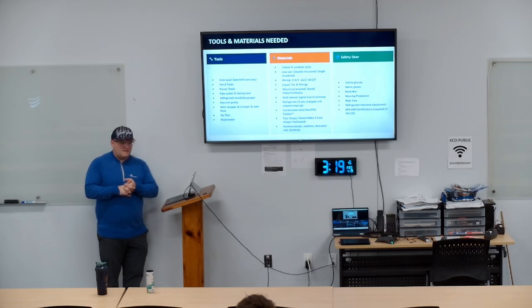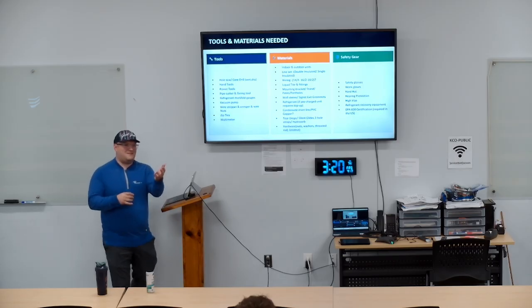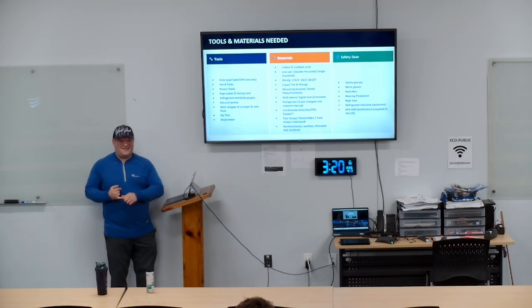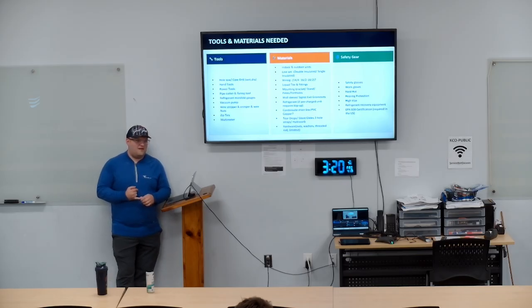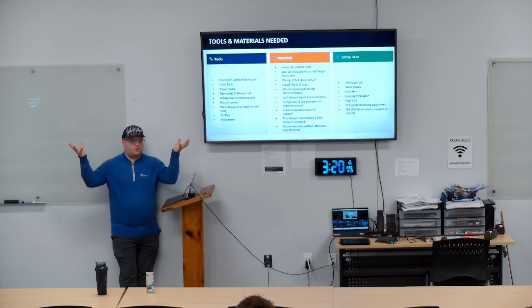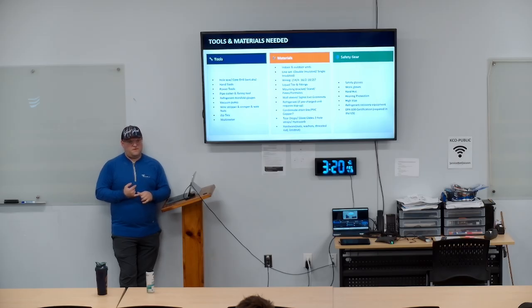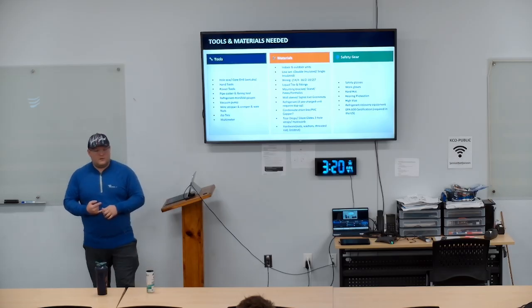Condensate drain. PVC or copper? Those are always questions. You cannot run PVC in a plenum ceiling. That's not code at all. So if you know it's a plenum ceiling, does anybody... our guys are probably going to be like, what's a plenum ceiling, Eli? Those ceilings where there's no ducted return. So you're supplying the air into the space, and a lot of the time you'll see just a return grill. So all that air is going back up. It'll work its way from one room to the next room to the next room till it's back up at the unit. So that conditioned air is technically in the space. They're using the space where we're running our stuff as the return, so all that air is flowing through there, cycling back out. The reason you can't have PVC is that if a fire ever happens, PVC, once it lights on fire, is poisonous, and it siphons right back into the space. So that's when we're using copper.